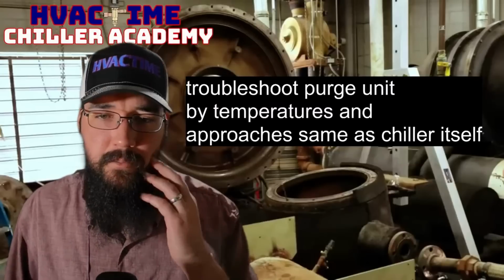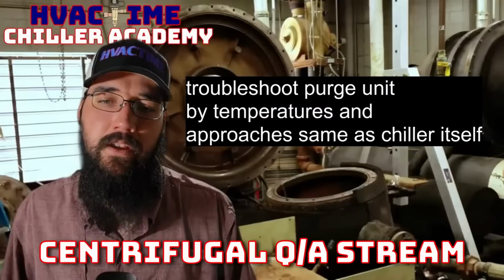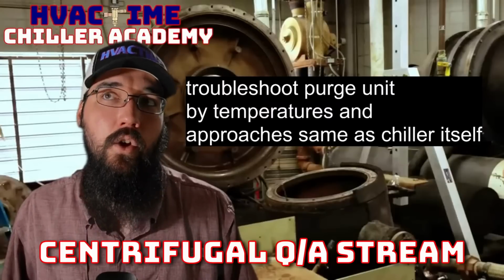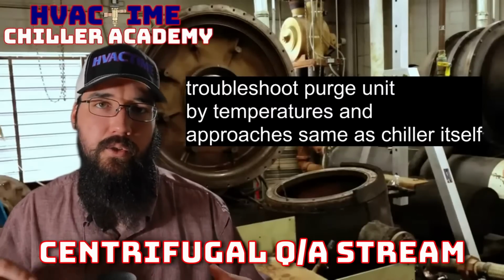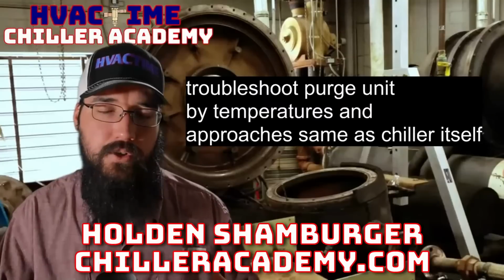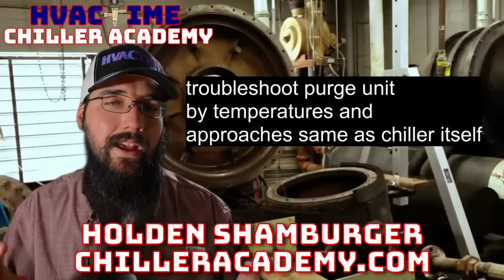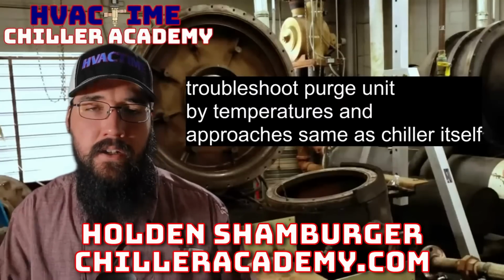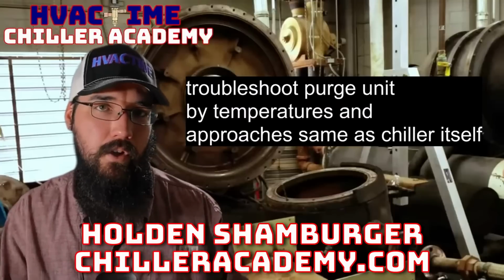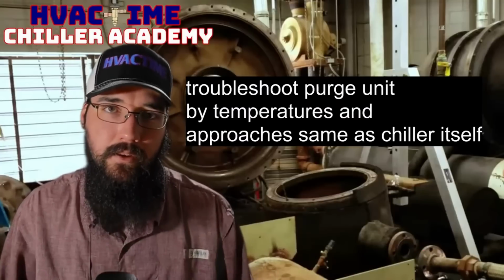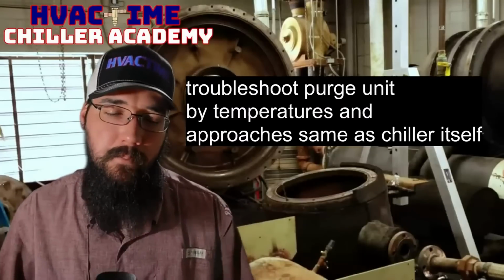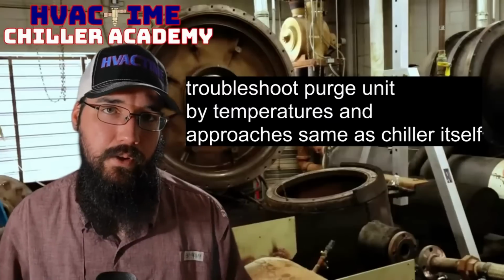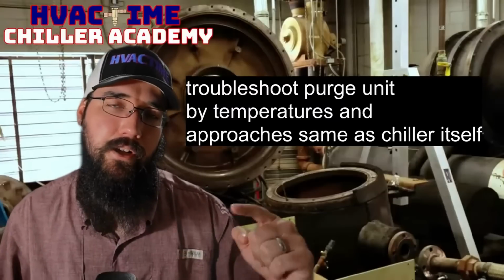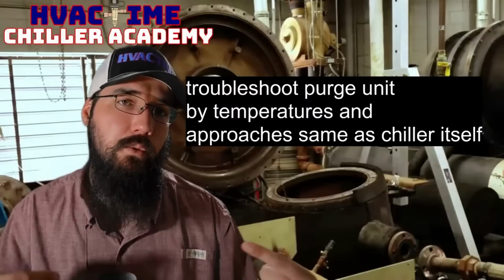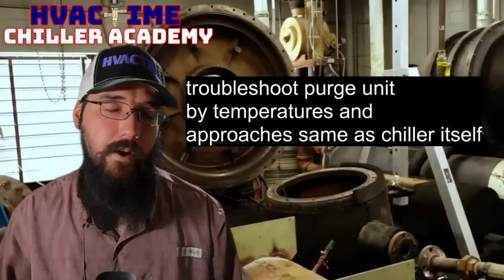All right, troubleshoot the purge unit by temperatures and approaches, same as the chiller itself. No, not really. The first thing I'll do is perform a leak search. Let's see if I can even find anything. If it's got enough refrigerant in it to ice up at all, which a lot of times they will, especially if they're having trouble, it probably has enough refrigerant in it to do a leak search. So I will start with a leak search with the refrigerant that's there.